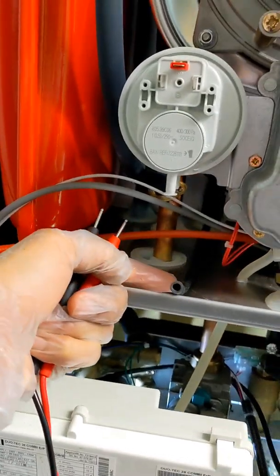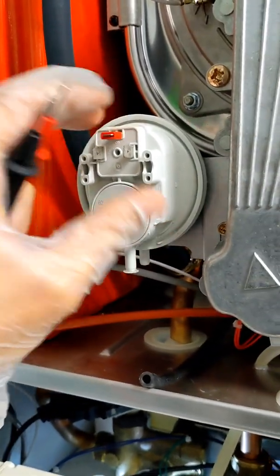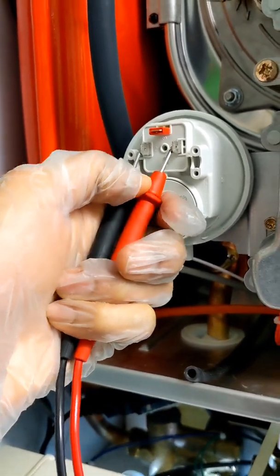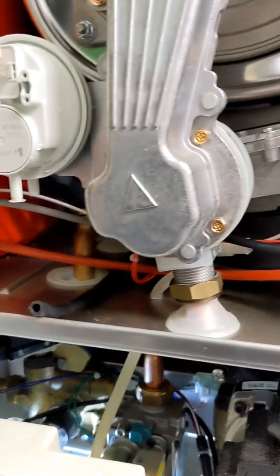So what was happening is condensate was backing up through there, going into the air pressure switch. At rest, this should have continuity across it, which we didn't have because the water backing up in here was breaking that switch. Now, if I put it all back together...